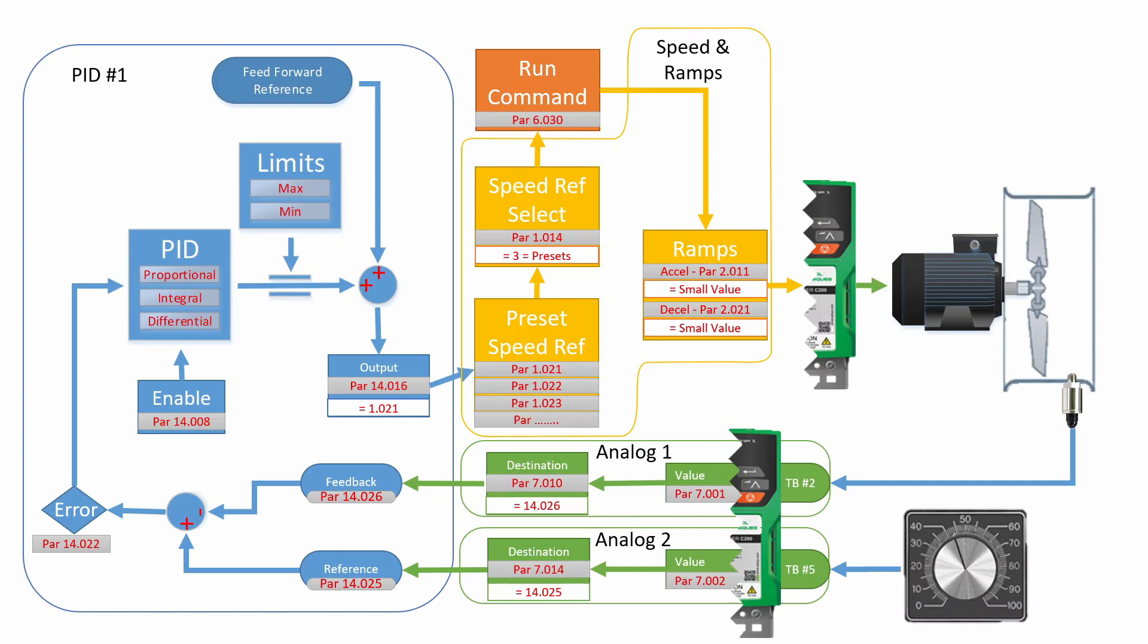That tells the drive that we're going to be taking our speed reference from the preset references. The drive will block the references if the run command is not on. After you give the drive a run command, the drive will send the speed that you have selected to the ramps. Now here you can see that there are two parameters listed, 2.11 and 2.21. Both of these values need to be very small. If they are not, they will interfere with the PID loop. However, some people use a very small value as a filter.